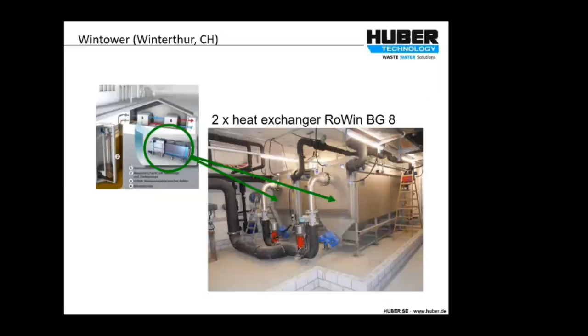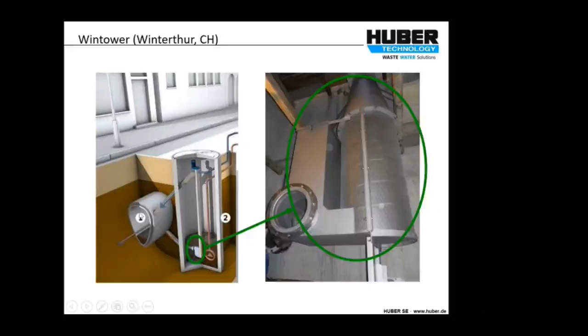As engineers, you might be interested in this, but that's a closer look at the 6mm screen. So you can see the perforations going up the side there, and the incoming pipe here. That's just a surge vessel up here. The sewage comes in there, goes in there, and if you magnify that, I can't magnify it, you would see they're 6mm perforations. And there's an auger inside there that carries the screenings up that pipe here and back into the sewer. So that's the heat pump associated with our ROWIN. Our ROWIN extracts about 3 degrees centigrade from the heat that flows into it, and then the heat pump will take that up to whatever temperature the building is designed for and the building calls for.